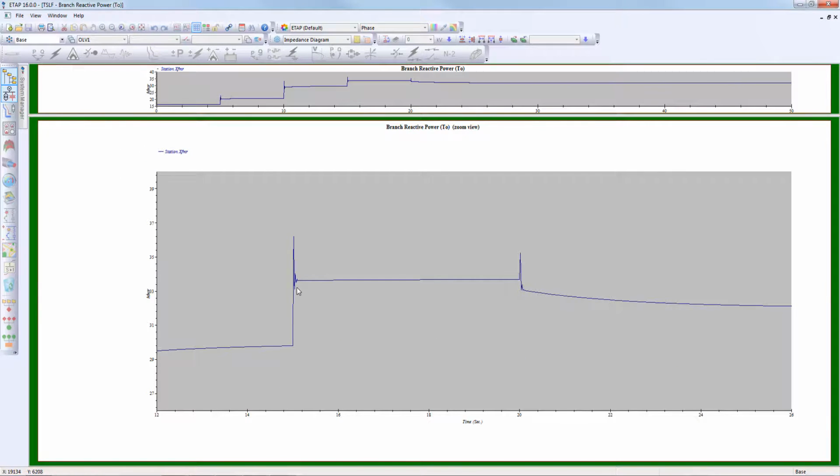We can observe that at each stage previous to the last stage, the reactive power output reached the desired operating value. However, on the last output at 100% active power generation, the reactive power capability of the wind turbines could not suffice and reach the final desired value, which is approximately 40 megavar.